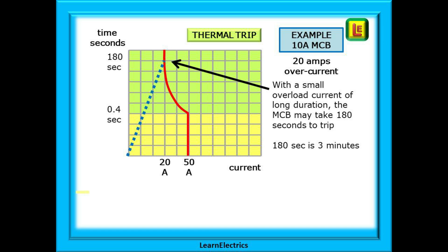In our example after 180 seconds the bimetallic strip has distorted sufficiently to operate the trigger mechanism and the MCB will turn off. 180 seconds is three minutes. A long slow response time but this is what happens.